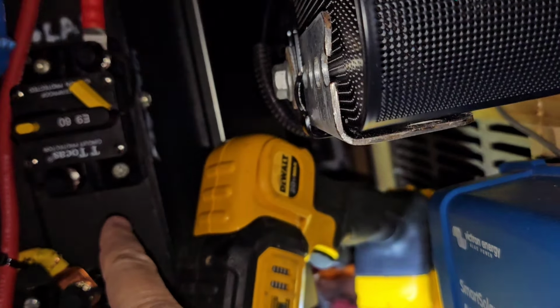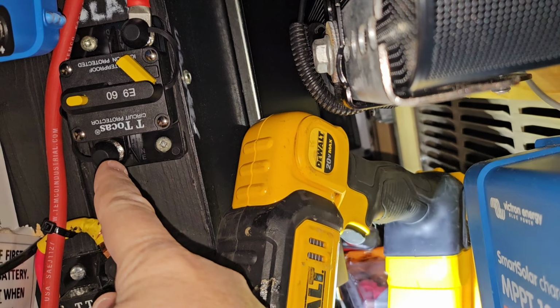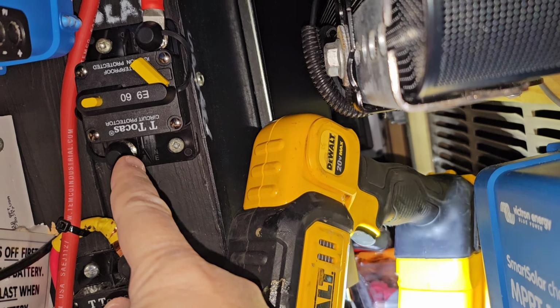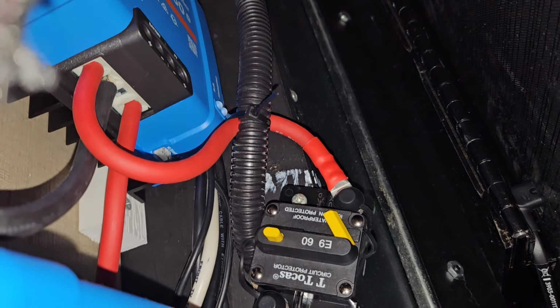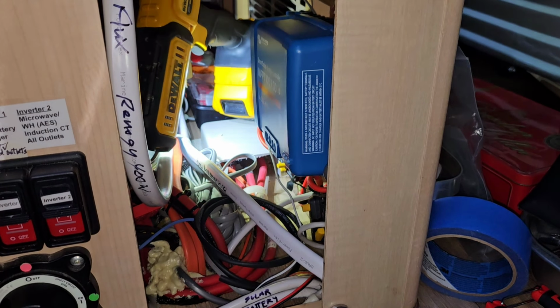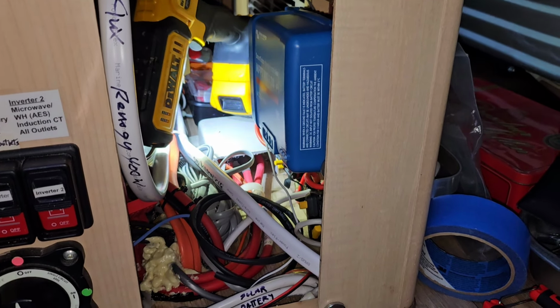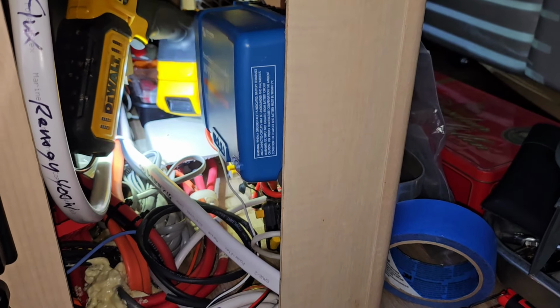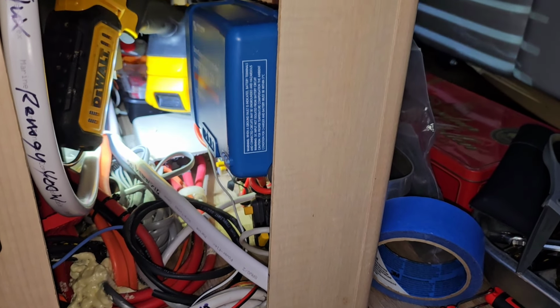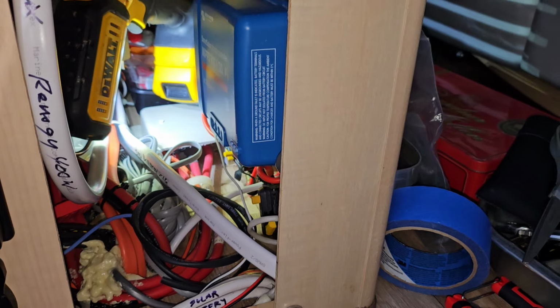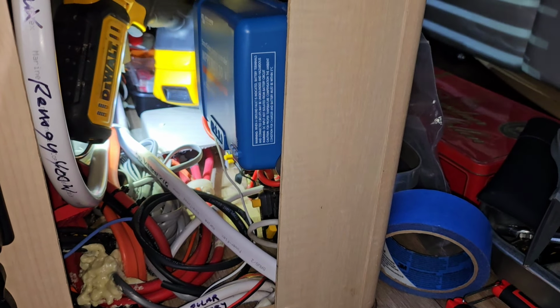It's going on this circuit breaker, and the negative is going to go up there in that solar controller. I'm going to use a couple of ferrules on the negatives to go into the solar controller, and quarter-inch 8-gauge lugs for my connections on the circuit breaker. So let me get on with that.